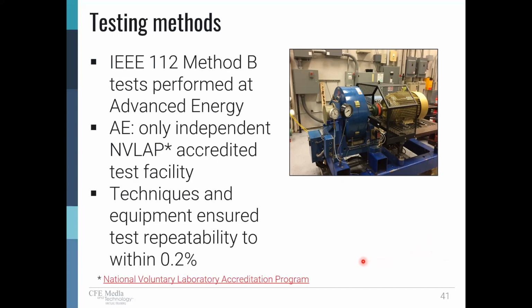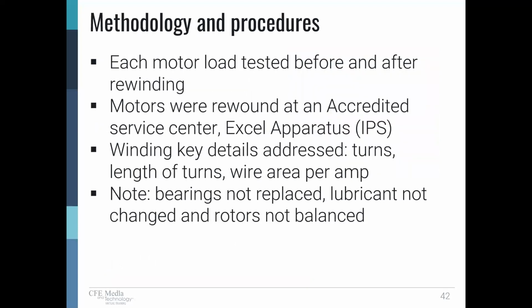And the testing that's done, whether it's done at a motor manufacturer lab or at Advanced Energy's lab, for example, if 3 different labs tested it, the equipment test repeatability, they'd find that the efficiency values obtained are all within 0.2%. That's actually pretty phenomenal if you think about it. The methodology: each motor was load tested at 100% load for efficiency before and after rewinding. They were rewound at an accredited service center. So one of the EASA accredited service centers did the rewinding.